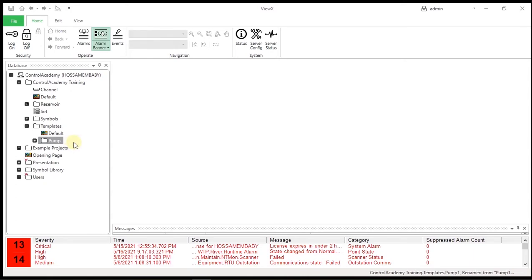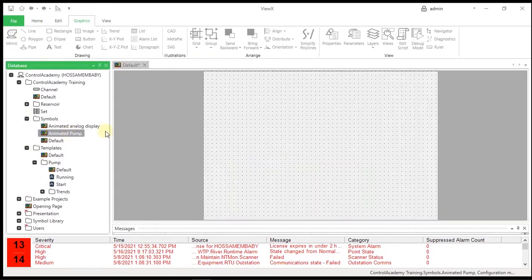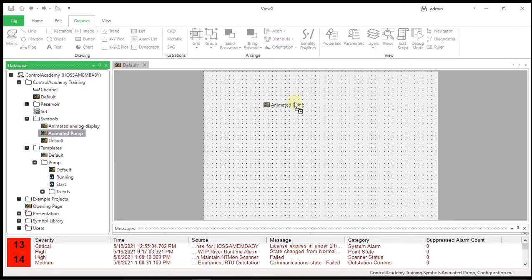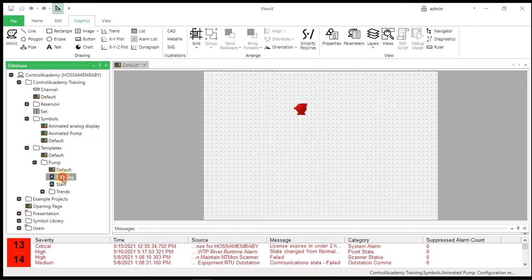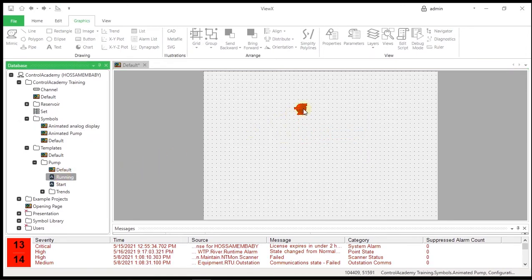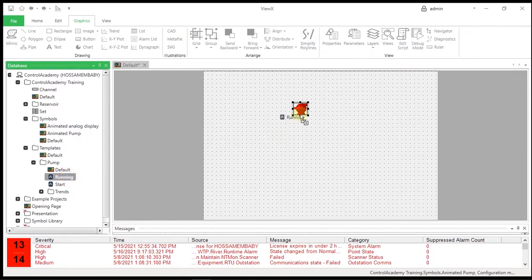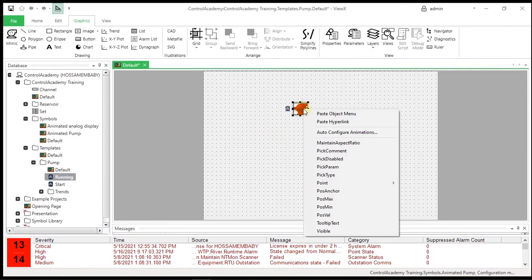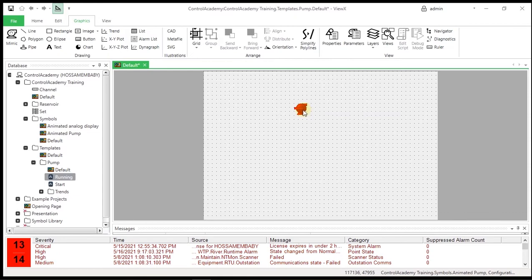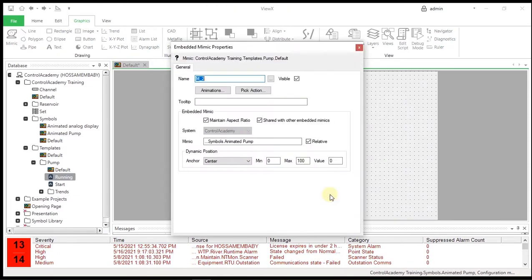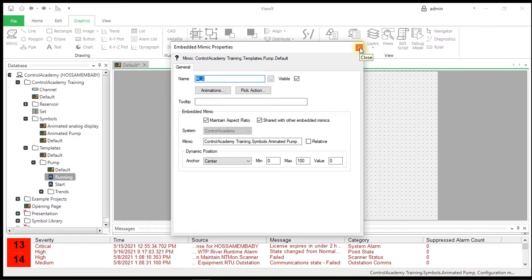On the Templates.Pump default mimic, embed the animated pump mimic that you created earlier in the Training.Symbols group and tie this to the running point in the new pump template group. Right-click the embedded animated pump and select Properties from the menu. Clear the relative checkbox so that absolute addressing is used. You should know that mimic references to items outside the template should always be absolute references.